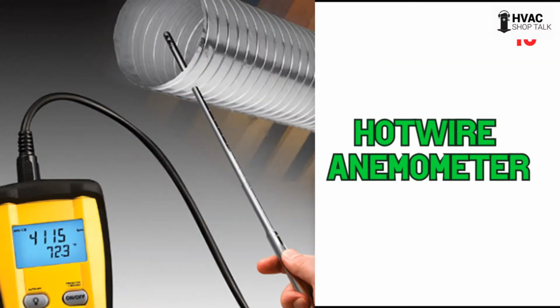Now, hot wire anemometer - here we see a Fieldpiece one. You've got this long metal probe with a sensor in the end. Basically, it's taking the temperature of that sensor - you have a hot wire probe. Just imagine it's hot, because that's the best way to do it, let's keep it simple. Air moving across it cools it down, and however cool it gets, that's what the velocity is - that's how it reads the velocity.